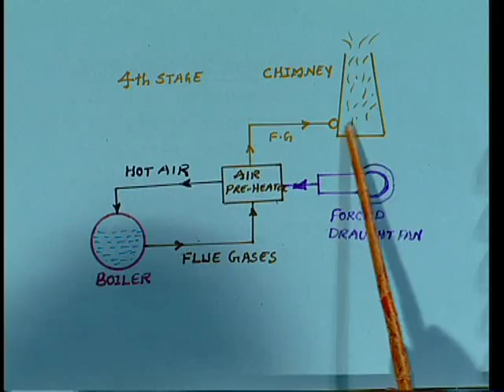So now this is the boiler, and flue gases are entering into the air preheater. This is the forced draught fan, and cold air is entering into the air preheater, where the cold air is converted into hot air by taking the temperature from the flue gases. That hot air is fed to the boiler for burning of the coal, and after taking the temperature from the flue gases, they escape into the chimney through the induced draught, and this chimney is left open at the top side.